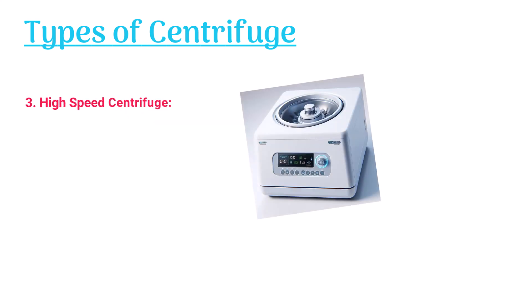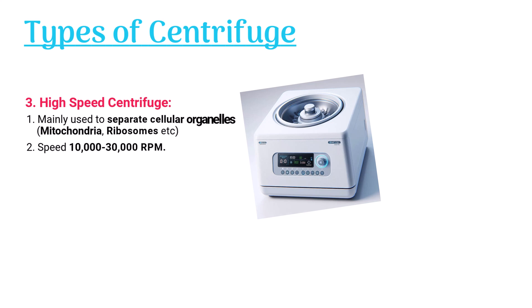The high speed centrifuge is mainly used to separate cellular organelles like mitochondria and ribosomes. Its speed ranges between 10,000 to 30,000 rpm.